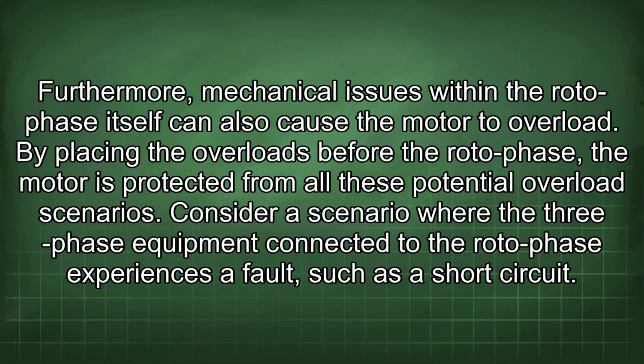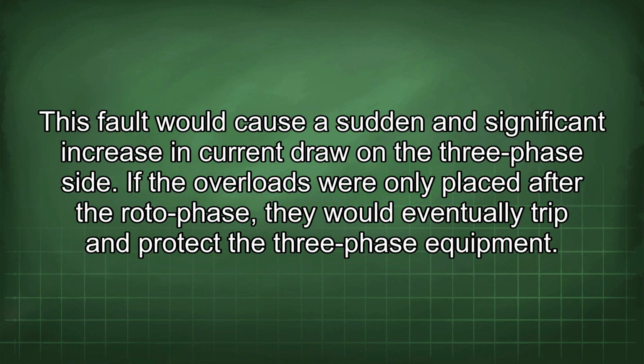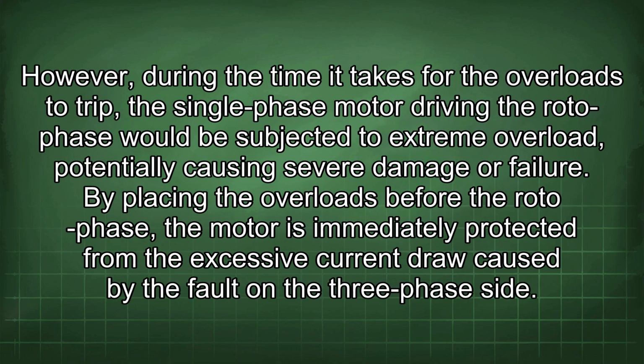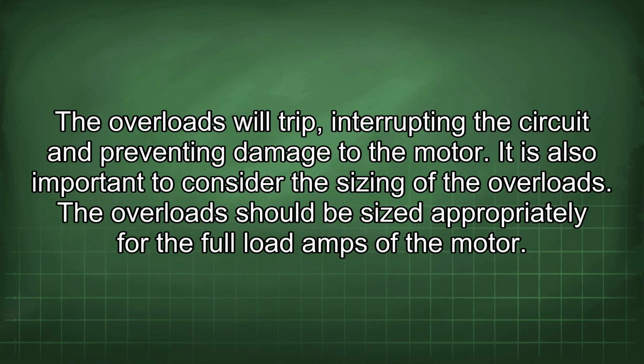Consider a scenario where the three-phase equipment connected to the roto-phase experiences a fault, such as a short circuit. This fault would cause a sudden and significant increase in current draw on the three-phase side. If the overloads were only placed after the roto-phase, they would eventually trip and protect the three-phase equipment. However, during the time it takes for the overloads to trip, the single-phase motor driving the roto-phase would be subjected to extreme overload, potentially causing severe damage or failure. By placing the overloads before the roto-phase, the motor is immediately protected from the excessive current draw caused by the fault on the three-phase side. The overloads will trip, interrupting the circuit and preventing damage to the motor.